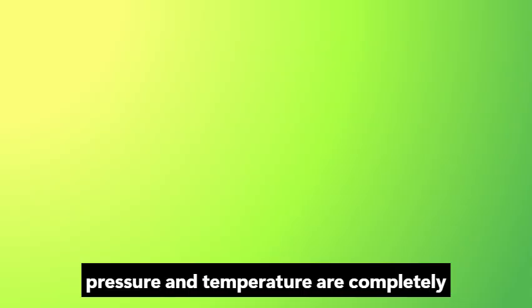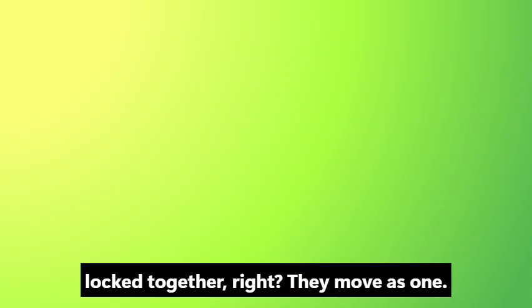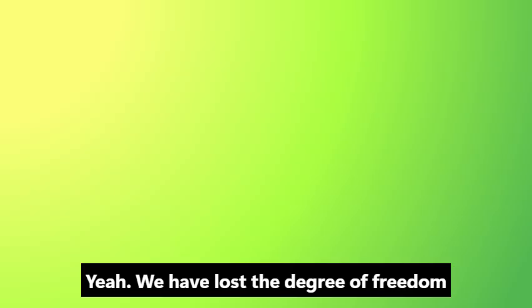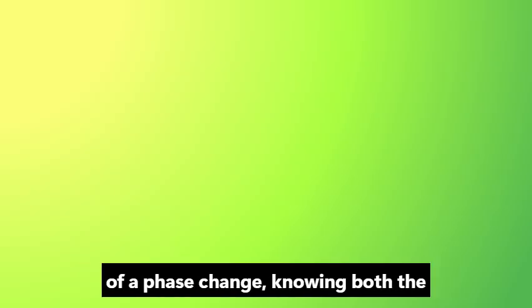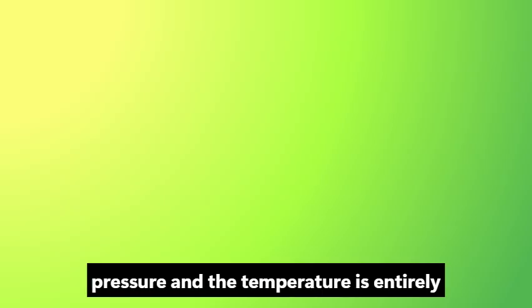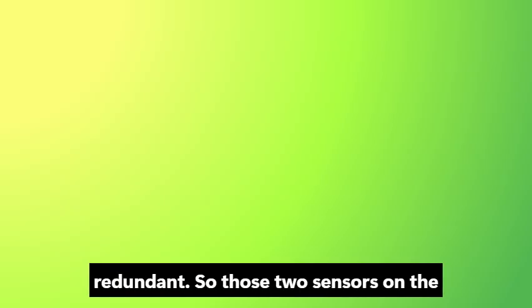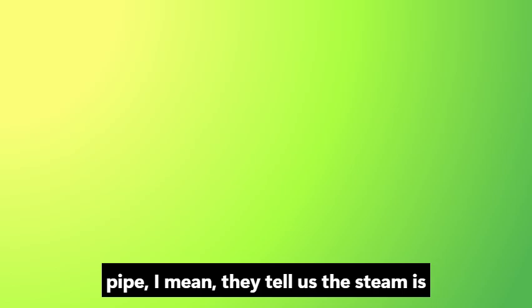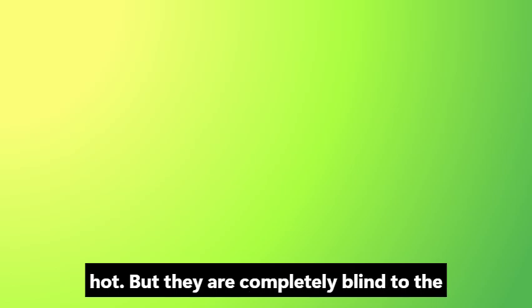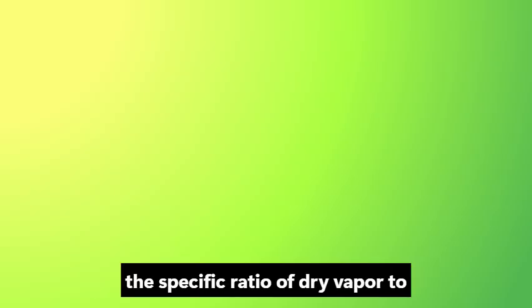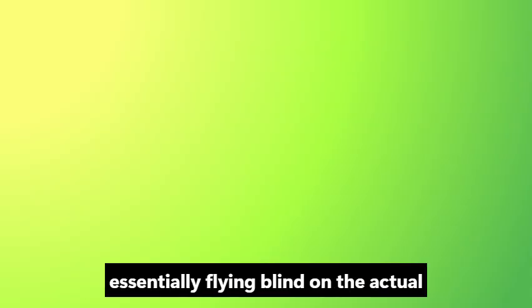What's fascinating here is that managing steam isn't just about making it hot. It's about controlling its exact quality or dryness. Because we're on that curve, pressure and temperature are completely locked together. They move as one. We have lost a degree of freedom in our system. Because we're in the middle of a phase change, knowing both the pressure and the temperature is entirely redundant. So those two sensors on the pipe tell us the steam is hot, but they're completely blind to the actual steam quality. They can't tell us the specific ratio of dry vapor to entrained liquid water droplets. So we're essentially flying blind on the actual enthalpy, the total energy of the system.